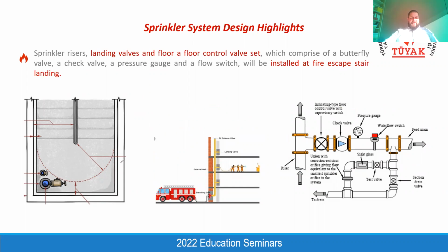in high-rise buildings, generally all of the doors are located on the same side. For example, sorry for my bad drawing, we have a door here, and the riser is always located there. But on some floor, maybe the entrance door of the staircase may be required to be on that side. In this situation, you have to inform the mechanical designer so that he will revise the location of the riser, and he should relocate the riser.